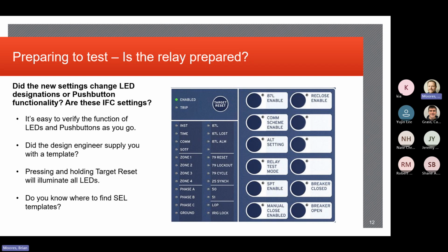All right, so this is just display points and LEDs and whatever, but it's absolutely important because this is now your interface. And this is what someone's going to walk up to and see. They're going to use it for some local control. They're going to use it for local indication. And this is generally the first place someone goes if there actually is a fault. They're going to look for these targets. That's what this whole lower left-hand column, 2 columns are basically targets. So we validate those as well. And again, those LEDs and those push buttons in that big logic diagram, that's all they are, is inputs and outputs. And their settings associated with what their functionality is.